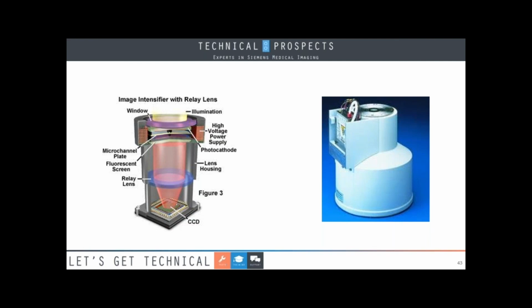So much better. But if you have an analog system with an image intensifier, you're going to want to check voltages. There's a little power supply, usually like right there, okay? And there's a test certificate that comes with every image intensifier. And you just basically go in and adjust it. And like any power supply, they're going to vary a little bit. So if you have an image intensifier, and you'll know because that's a pretty big thing standing on top, you'll know. The first thing you're going to want to do is see how your power supply is, because it'll throw everything off.